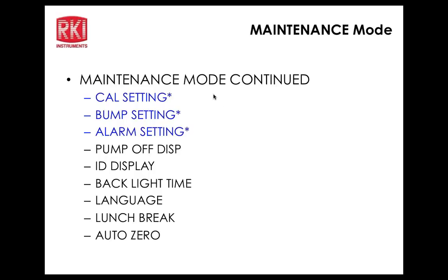That gets us back to the main maintenance menu. The next is bump settings, the second submenu capability. We have bump display. What that means is if I turn that on, bump will come up as an option in the display button function. There are several settings you can have appear or not appear when going through the display button function from the normal operation screen.